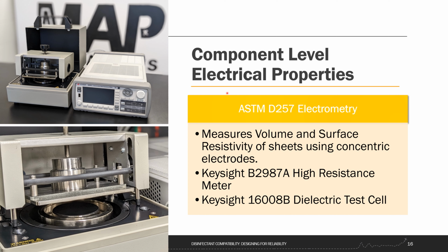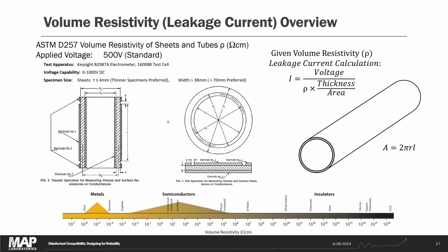Here our focus is mostly on electrical properties, so we're going to jump into ASTM D257 measurement of volume resistivity of our materials after disinfectant exposure. ASTM D257 describes test methods for measuring the volume resistivity on sheets and tubes. You can then use the measured volume resistivity rho, the thickness of the material in question, and the surface area of the material in question to calculate the expected leakage current for your material. You can measure that resistivity after 8 minutes of disinfection, after rinsing, after prolonged soaks in disinfectant, and to determine which materials are going to be best and which disinfectants are potentially going to be problematic for you.